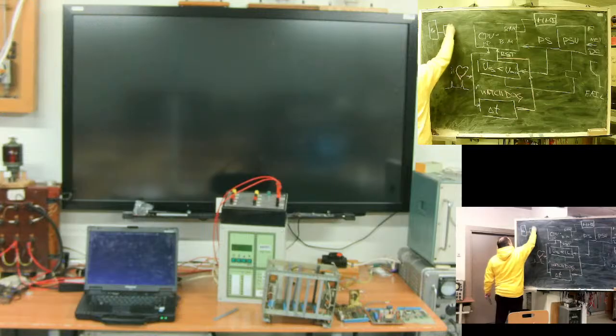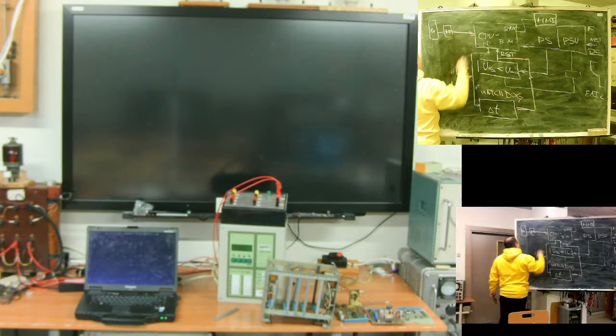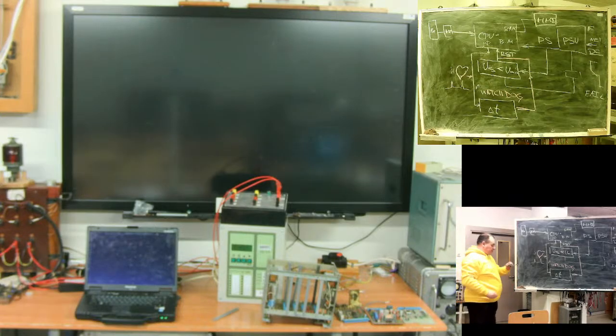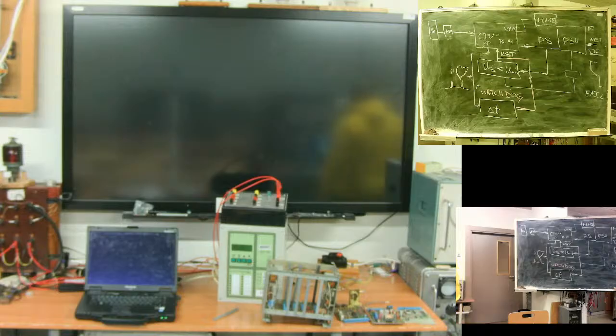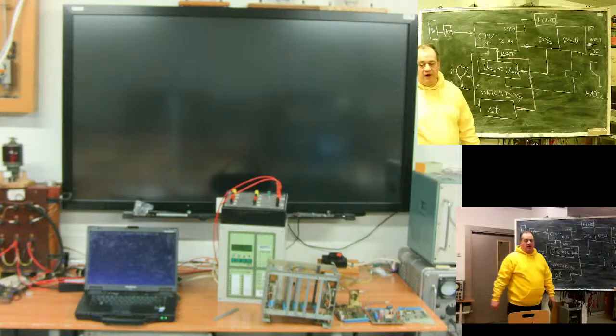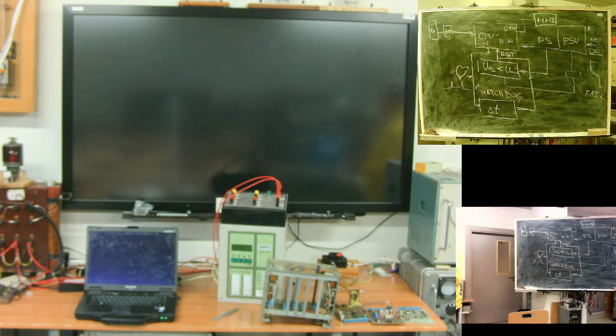Analog part, ADC, data. Fine. But what is this part? When we look at our device, inside the logic of our device, it does something if something. What is the something in the if? Disconnect line if current exceeds. For this device, start if current exceeds and calculate fault distance. Yeah? What should the device know?